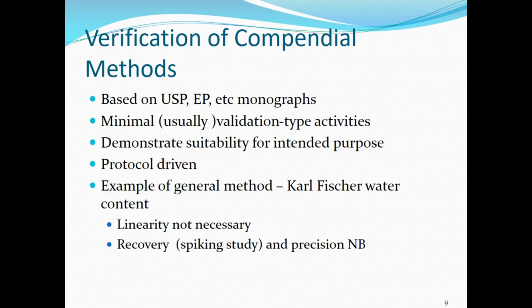We don't necessarily validate these compendial methods, but we are required to verify them for use in our own laboratory. Verification of compendial methods is usually for methods that come from the USP or the EP, the European Pharmacopoeia, or other monographs. Minimally, the verification that's required usually replicates some of the validation activities that we would carry out. You need to demonstrate that the compendial methods are suitable for your intended purpose on your compound in your laboratory.